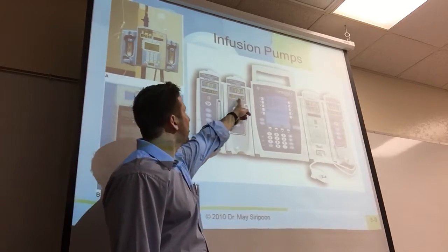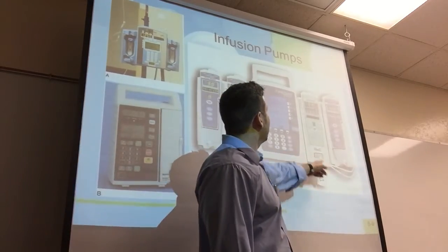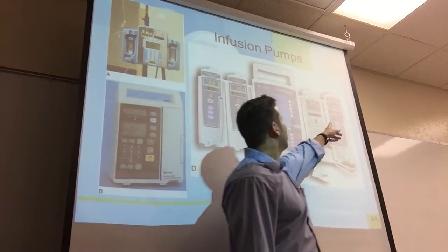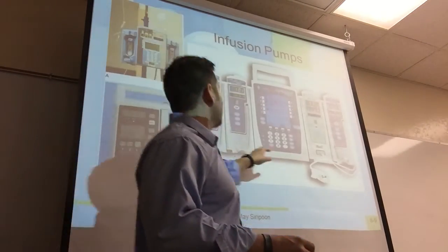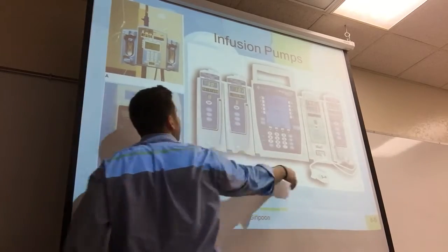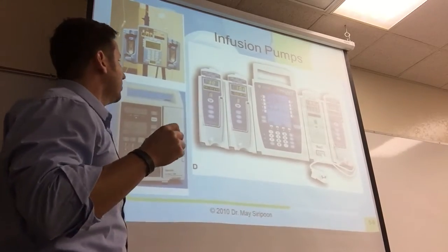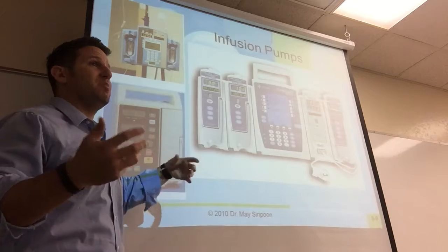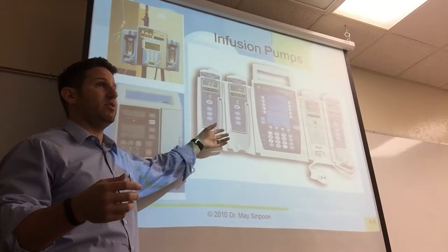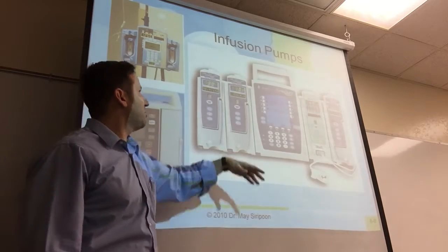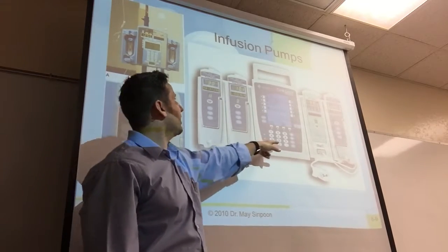Now, this one's pretty cool. If you notice here, this one says lidocaine on it. This one has a pulse ox on it. This one says it's the medication name. So when you do it, these are actually detachable. Pretty cool. And so all you have is the brain, and as you need pumps, you attach them. You can attach up to 4 to a channel, 4 to a brain. So you just clip them on there, and then you program it at the brain.